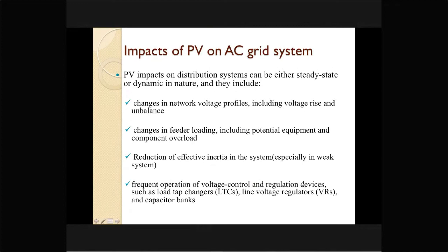So when we go for photovoltaic and integrate that into the grid, the impact of photovoltaic can be manifold. The impact on the distribution system is there in both steady as well as dynamic nature. The change in network voltage profile, which includes voltage rise and unbalance, will be one of the impacts of photovoltaic integration into the grid.